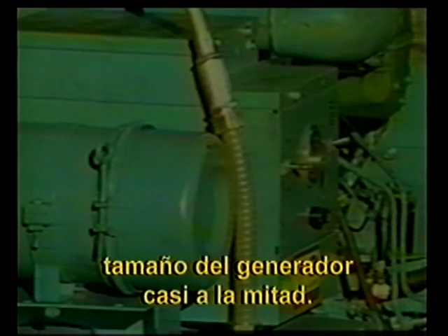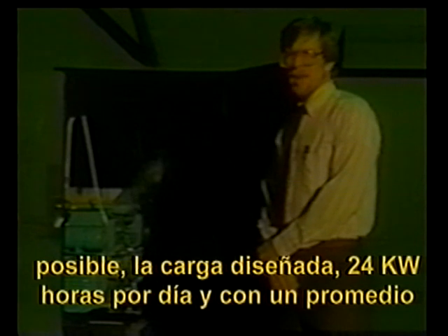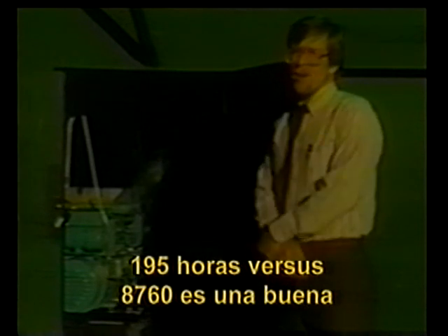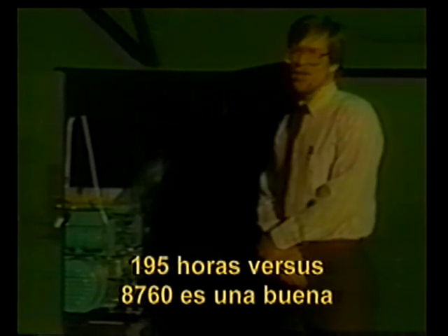Now with the photovoltaic system and only needing the gen sets for backup, we've reduced that generator size almost in half. In our calculations in designing this system, at the worst possible load, the design load, 24 kilowatt hours per day, and with the average inclement conditions during the winter, this backup system will run a maximum 195 hours. 195 hours versus 8,760 is quite a comparison in fuel savings.